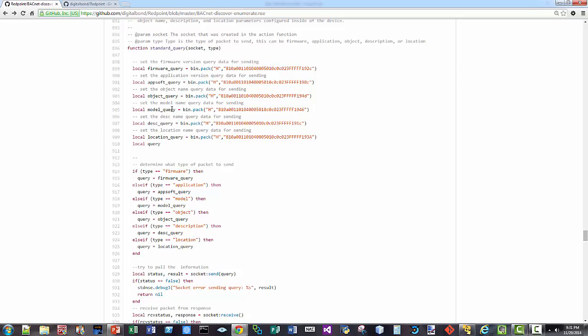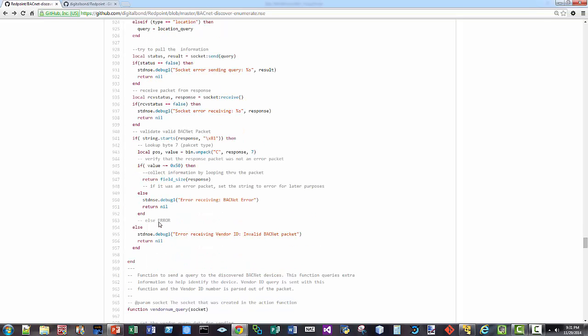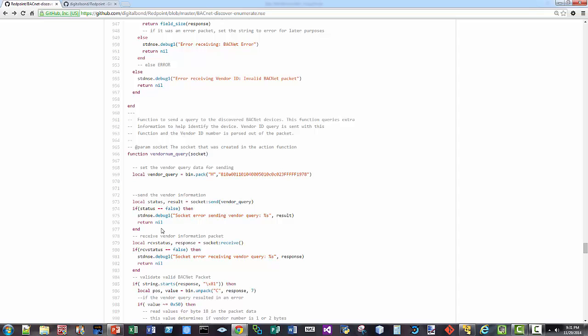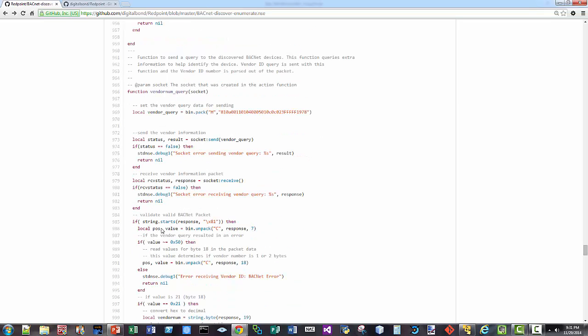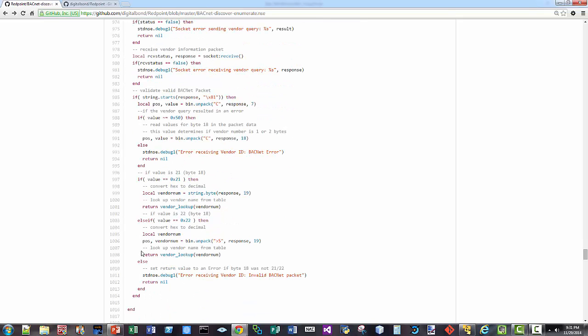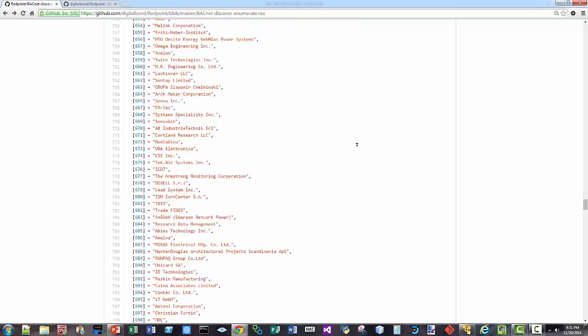It's going to parse through these. It's going to do queries, and it's additionally going to try to connect if it can find any points. It's going to try to connect to those points, and it's going to try to actually enumerate points, try to see if it can get any points and data associated with those points. Basically, a BACnet IP device will have BACnet ID, and then it'll have BACnet points underneath it. And those BACnet points are what actually control the building.